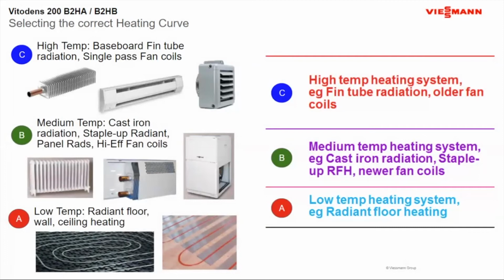So this is right out of the manual itself as well. And this is just showing you your different emitters on the left-hand side. And A, B, and C is just explaining what kind of emitters they are. So the A is normally going to be your radiant floor, your in-floor radiant. Medium temperatures could be your Runtal or fan coils. And then high temp could be high output baseboard, single pass fan coils. Excuse me.